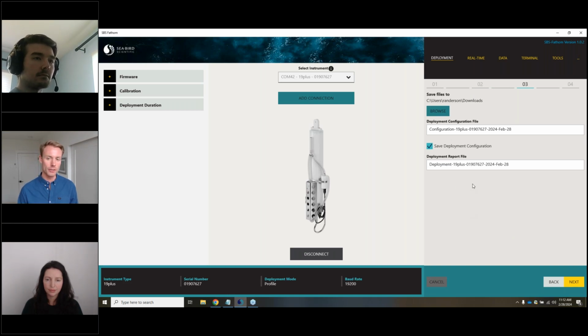This panel is going to generate two files for us. One is a configuration file. This is a new file type, new to Fathom. Basically, this is a configuration file that's going to be generated, it has all the settings that we just put in, and you can use it to deploy another instrument. So let's say I had a bunch of 19 pluses that I wanted to be deployed the same way. You can use that configuration file to make sure that all the settings get onto each instrument identically. The report file also has all those settings that were successfully sent to the instrument, and then a readout of all the settings and all the configurations that are currently the configuration of the instrument.